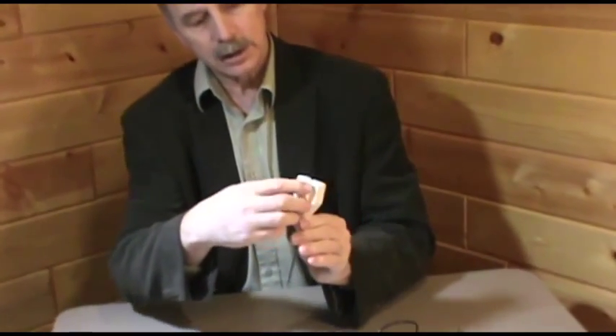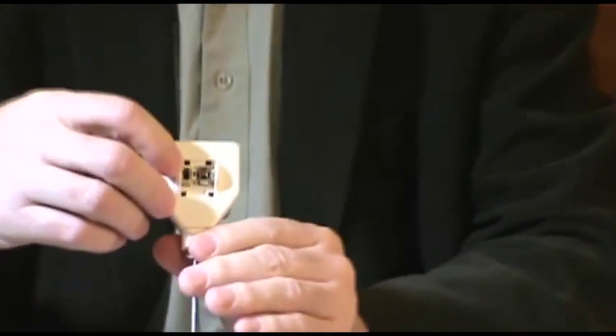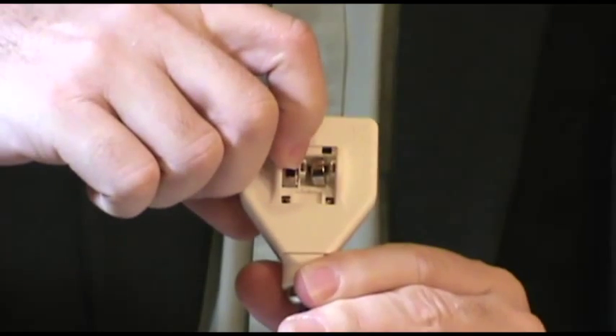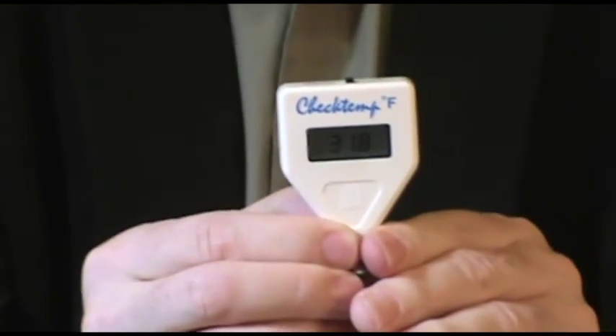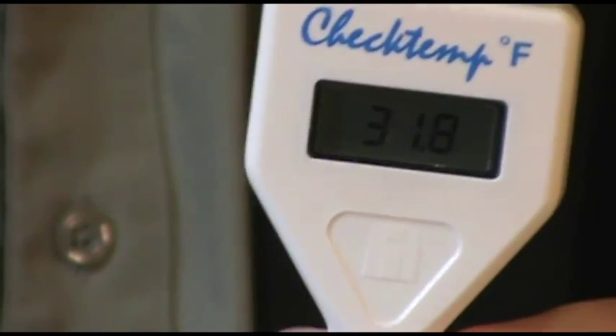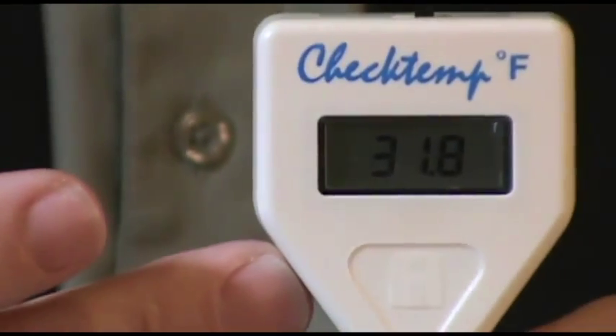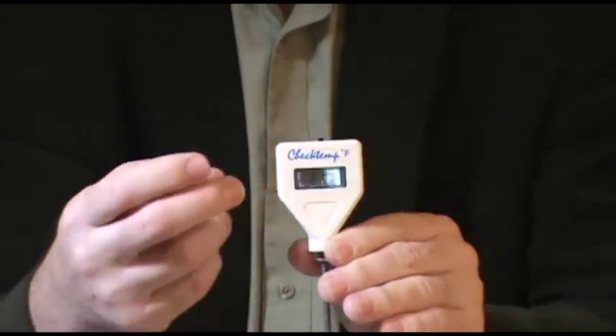Now in the back of this one, there's a battery cover that looks like this. You just take that battery cover off, and there's a black button in the back. It's the AccuCheck feature. Now the AccuCheck feature is built into the thermometer. No longer is it reading what the temperature of the tip of the probe is. It's reading a preset accuracy checking feature that's built into here, and it says that it's 31.8. It's checking to 32 degrees. It says it's 31.8. So this is verifying that it's 0.2 of 1 degree accurate, which is very accurate.